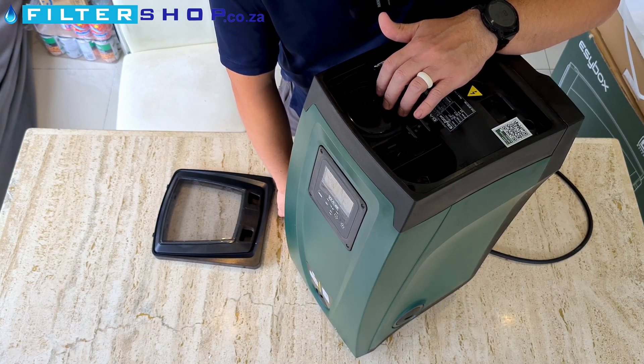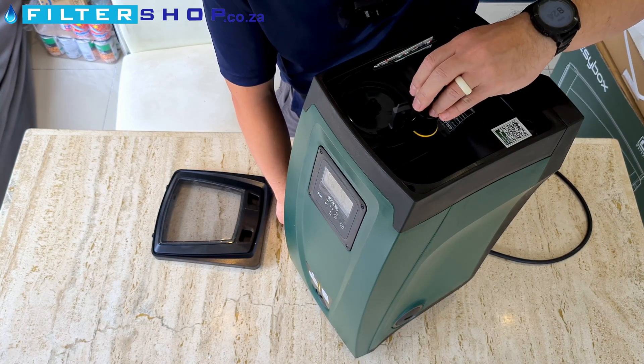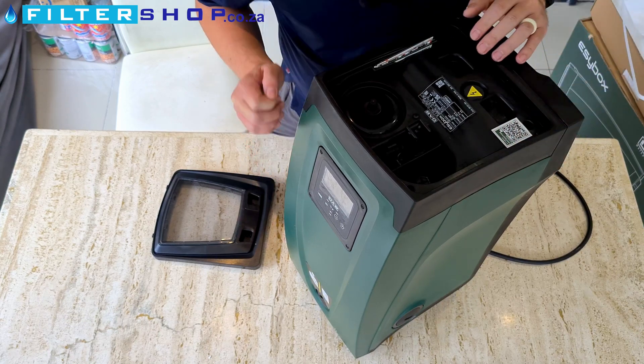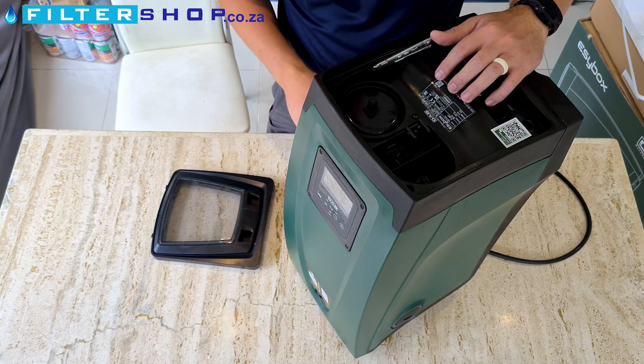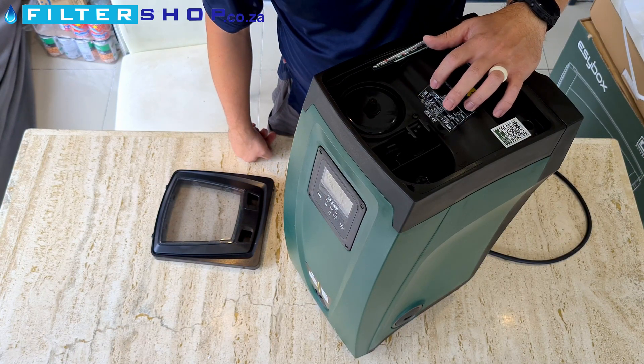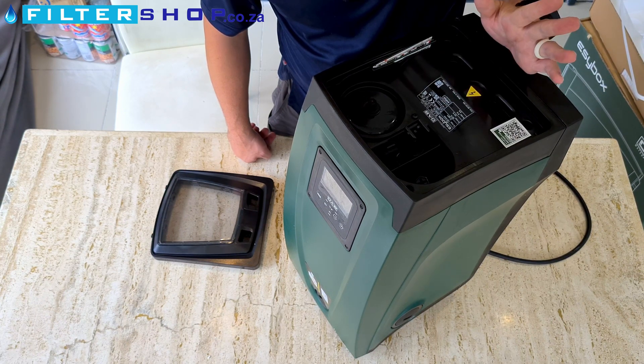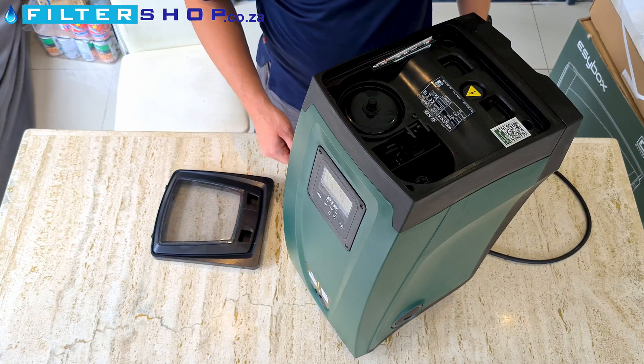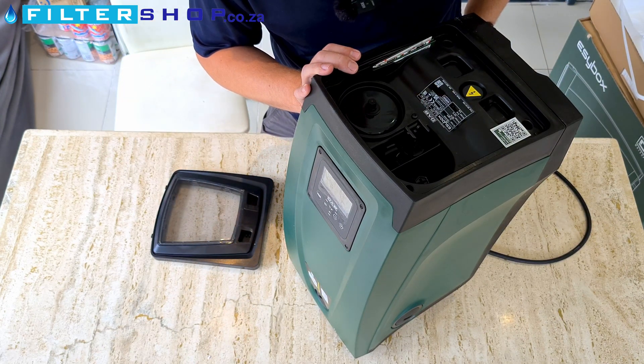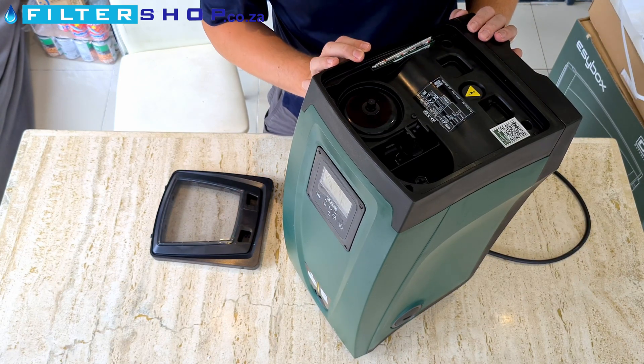Here's the service port for the tank. It comes with a little toolkit to do certain functions. Looking at the specs: it's a 1.1 kilowatt power-rated pump, but the input power is rated at 1550 watts. Maximum height is 60 meters, so 6 bar. The nice thing is you can do up to 8 meters suction with this, so if you have an underground tank, both this one and the Mini are awesome options. The Mini is basically just a shrunken-down, slightly lower-specced version of this.